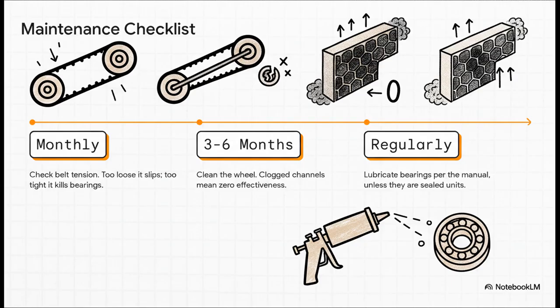First up, every month, check the belt tension. Too loose, it slips and wastes energy. Too tight, you'll destroy the bearings. Next, every 3 to 6 months, the wheel itself needs cleaning. If those tiny channels get clogged with dust, your efficiency can drop all the way to 0. And finally, you've got to lubricate the bearings according to the manual. These are simple, basic steps, but they are absolutely critical.